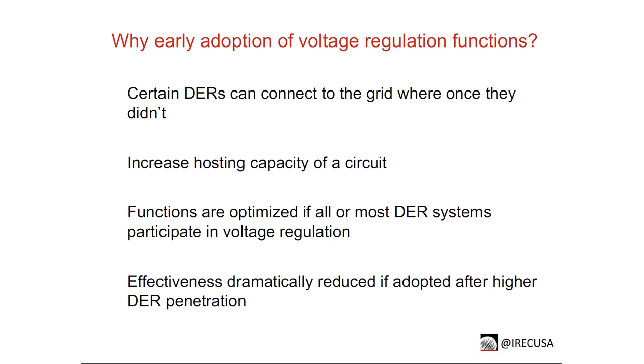Third, the effectiveness of voltage regulation can be optimized if most or all of the DERs are participating in voltage regulation. It can be very challenging to turn on the voltage regulation function in the future. If you reach a high penetration scenario and haven't turned on voltage regulation for any of those DERs, you've basically lost the opportunity, or it becomes very difficult and cost-ineffective to do so thereafter. And if only a small number of them are able to respond to voltage regulation, it doesn't really address the high penetration scenario.